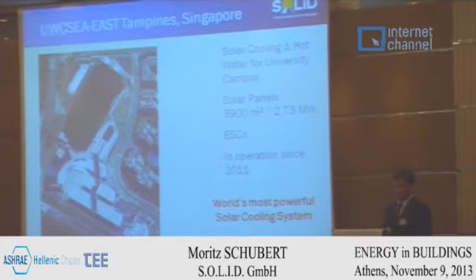It took us some days and weeks to balance all the flows to match the temperature requirements, because we have several hundred parallel flows. Each of these flows is only supposed to have a certain delta T in order to run most effectively, and also not to have too high or too low pressure loss.